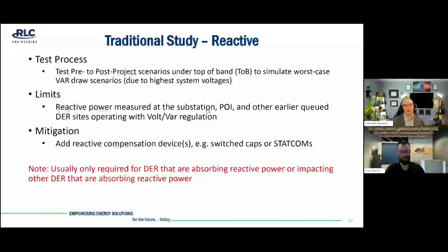For the reactive power evaluation, this is a pre to post project scenario. It's typically only evaluated if you are running off Unity or if you have other projects prior to this that are running off Unity. And you look pre to post project, we typically run this under top of band or ToB to simulate worst case VAR draws if you have volt VAR systems or volt VAR DER that are operating within volt VAR on your system, because that's going to present the highest system voltages and the most reactive power that you'd be absorbing.